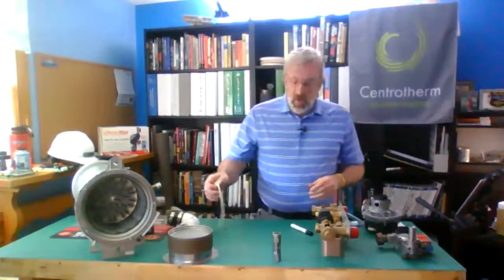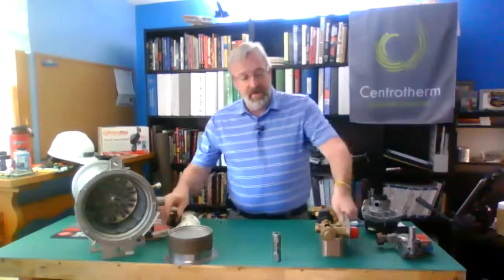I'm going to say that the number one call that I get in dealing with these is on the domestic hot water side. So there's a couple of points that are important when we talk about domestic hot water on the Noble. First of all, you absolutely must positively have a mixing valve on the outlet side of your domestic hot water. The reason is the boiler wants to kind of run, and so it needs a range to run in. If the boiler's got to sit there and hold 120 degrees dead on, it really can't. It likes to be able to ramp up and ramp down. We want to put that mixing valve on there.